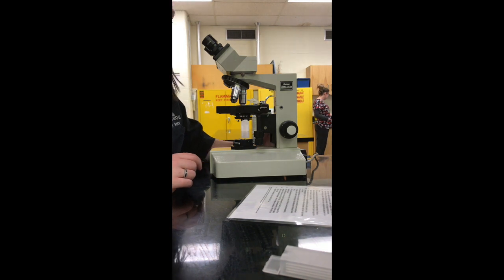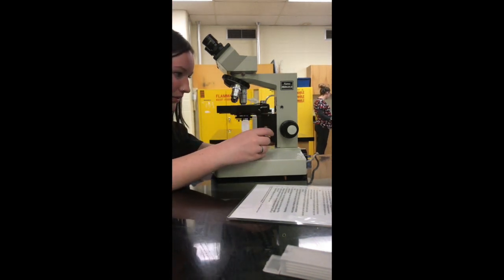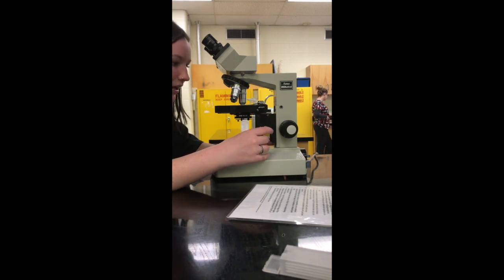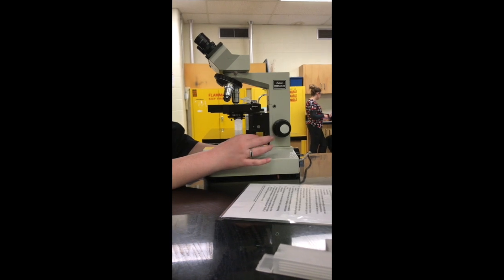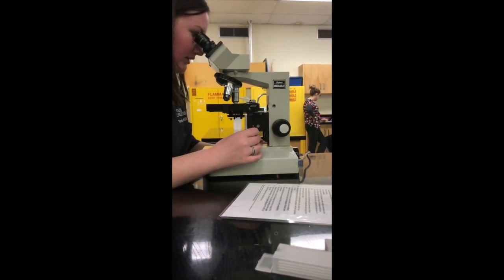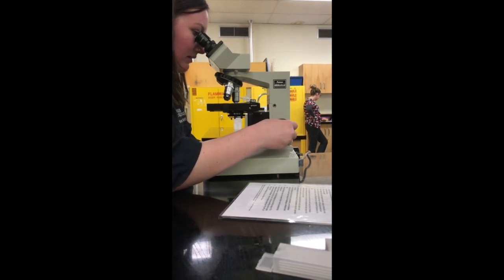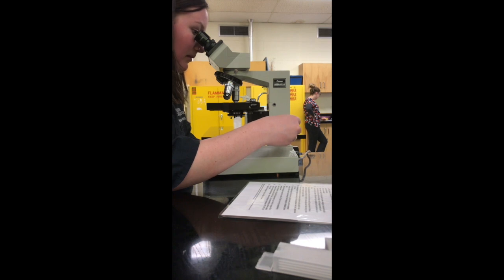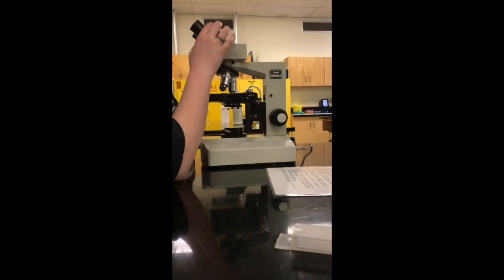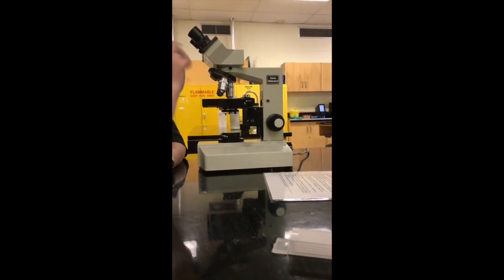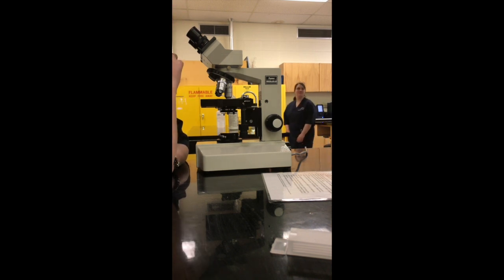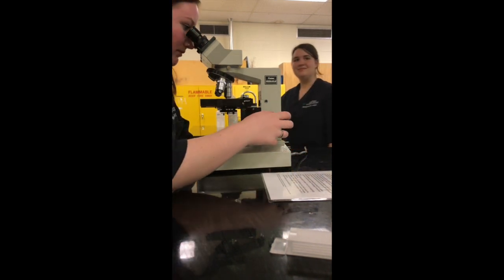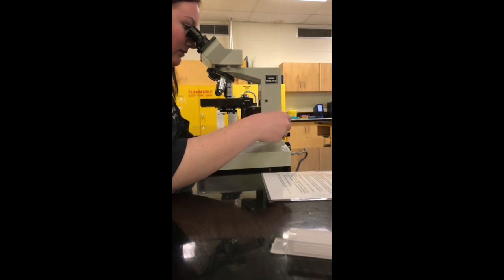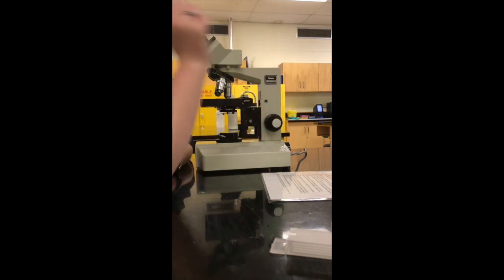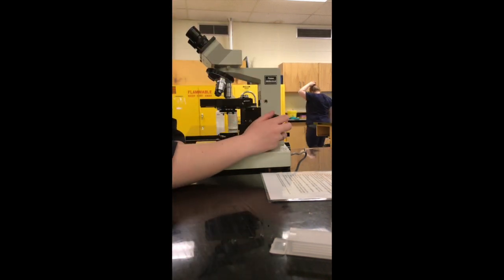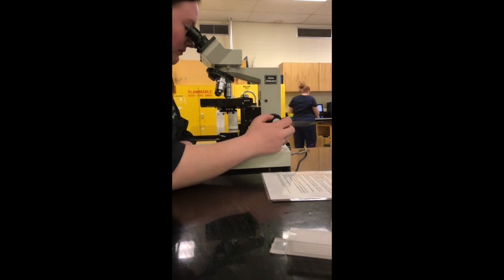And now I'm going to focus on the specimen. I'm going to move the stage so it's focusing on the feathered edge of the specimen, and now I'm going to focus it. There we go. I'm going to rotate the diopter ring on the right eyepiece to the same reading as the interocular scale. And I'm going to close my left eye and focus the microscope with the fine adjustment knob. Okay. And I'm going to do that same step but with my right eye closed and focusing with the fine adjustment knob.